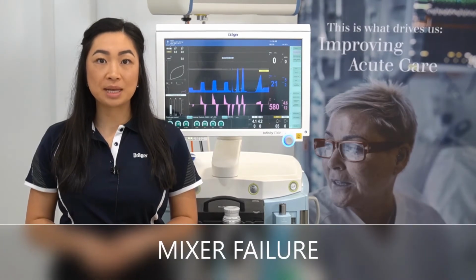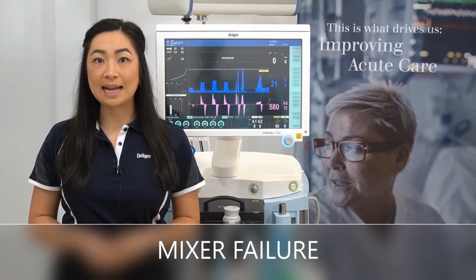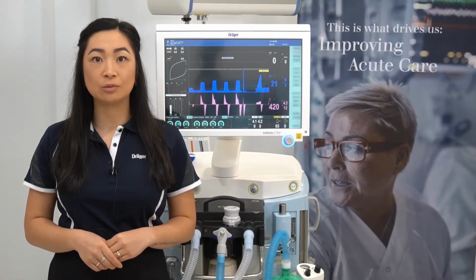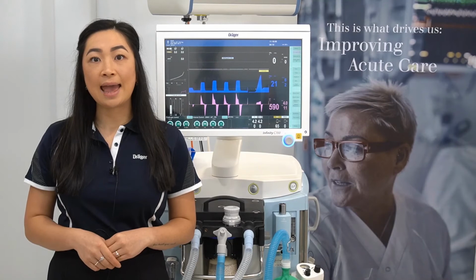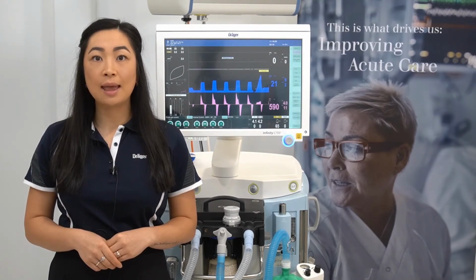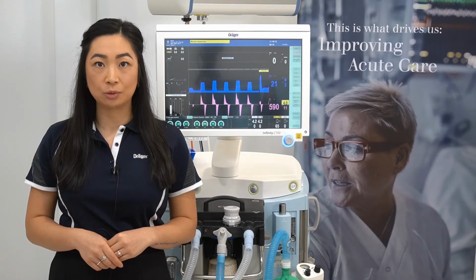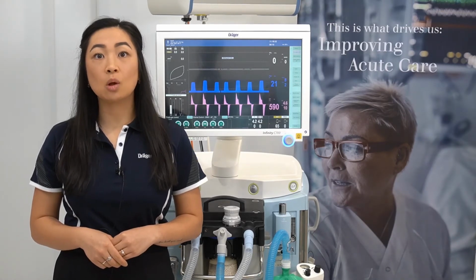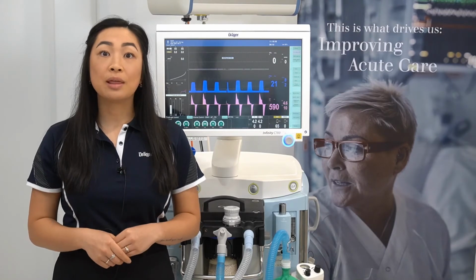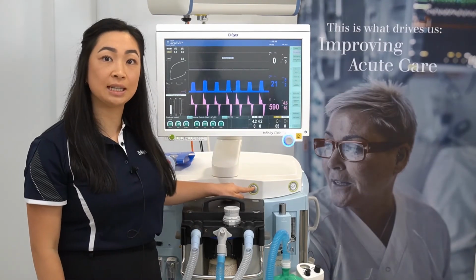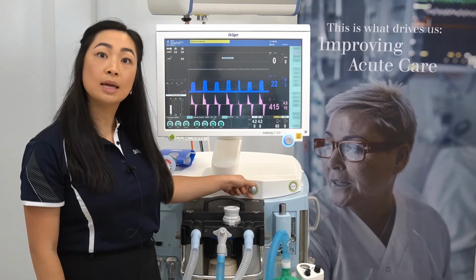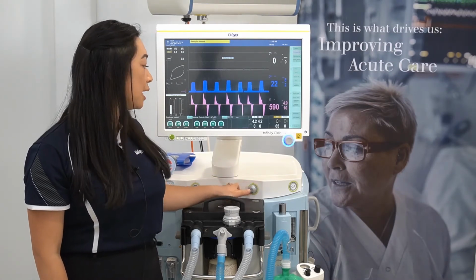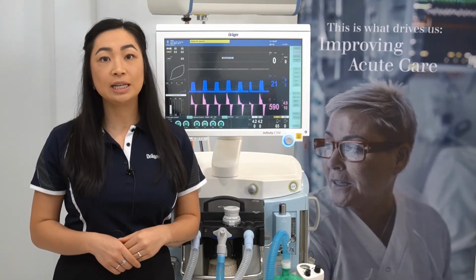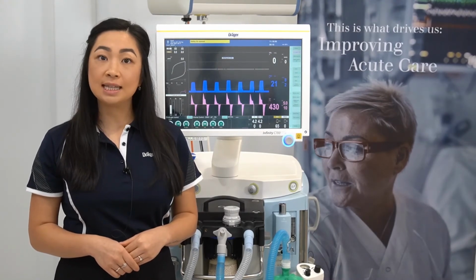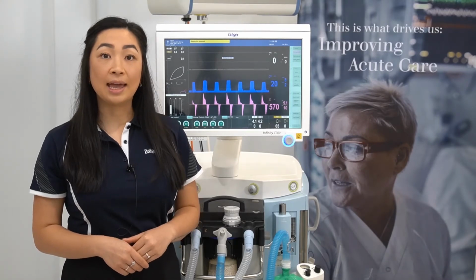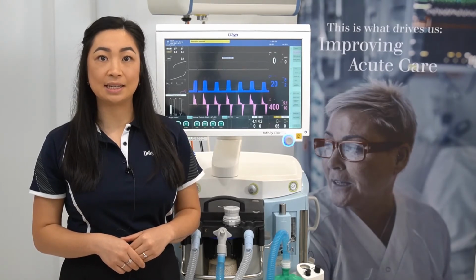In the event of a mixer failure, gas delivery and gas mixing will be switched off due to internal device errors. This means that air oxygen or nitrous oxide gas mixing delivery will be unavailable. The DIVA metering modules will also be unavailable. You will then need to activate your emergency oxygen delivery by pushing in the control knob, dialing up to your desired flow with the flow indicated on the outside, and transitioning to intravenous agents. Ventilation will not be affected. Then, contact your technical service representatives.